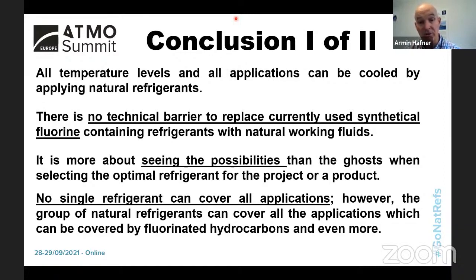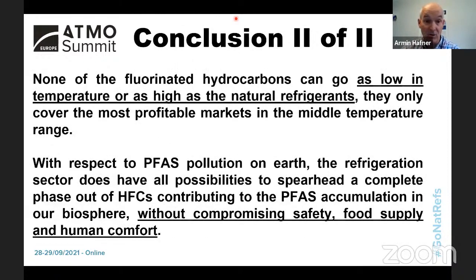But we can see that the natural refrigerants can cover all applications which are covered by the HFCs today, and even more. We can go lower and higher, because none of the fluorinated hydrocarbons can go as low in temperature as we can with the hydrocarbons, and as high as we can also with the hydrocarbons. These HFCs mainly cover the most profitable market currently, in the middle temperature range. When it comes to this forever chemical pollution we are introducing nowadays on Earth, our sector, the refrigeration sector, has all the possibilities to spearhead a complete phase-out of HFCs, which contribute to this forever chemical accumulation in our biosphere.